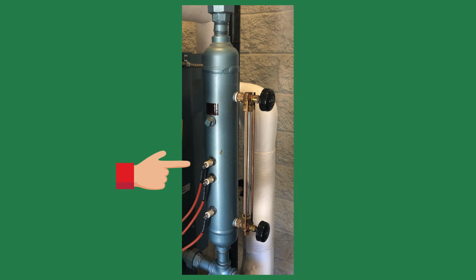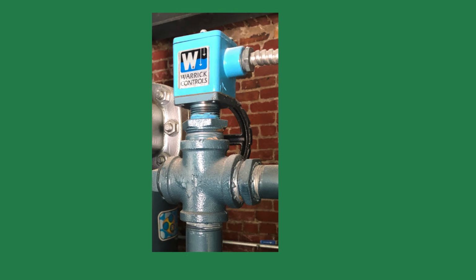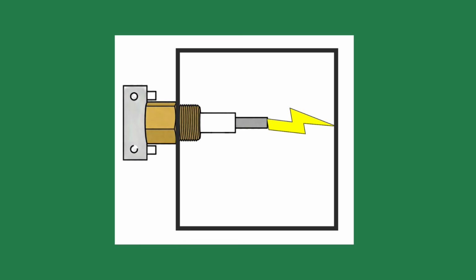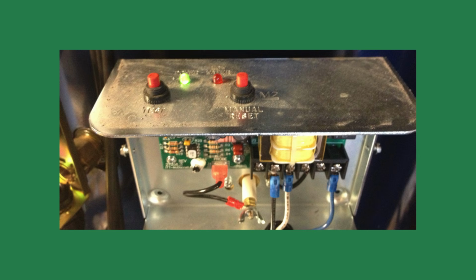The probe type, also called electrode or conductivity type boiler low water cutoff, uses one or more probes inserted directly into the boiler or piping. These probes are electrically insulated except at the sensing tip. A safe, low voltage, usually 24 volts AC, is applied to the probe. When the probe is surrounded by water, it completes the circuit and tells the burner it's okay to fire. Essentially, it's a short circuit. If the boiler water level drops below the probe, the circuit opens and shuts the burner off. I still wonder how many R&D folks got a little shocked during testing when they figured out which voltage was right.